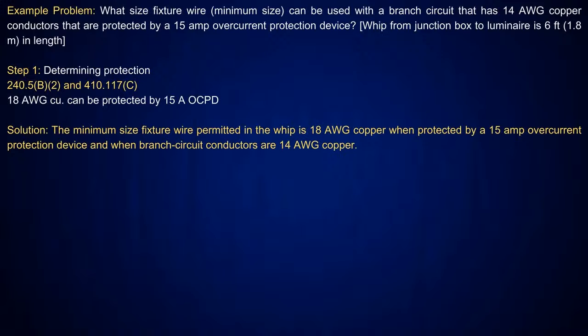Do you know why they permit you to use number 18 gauge or number 20 gauge on the fixture whip to the junction box? Because it's already been listed and labeled in size for that size wire. They know how much amperage it's pulling. Because it's technically a tap. It's not really a tap. It's a tap conductor. I'd be careful calling that a tap conductor.